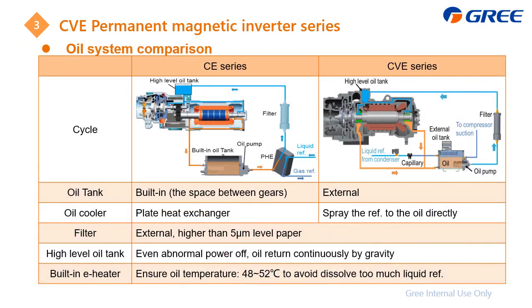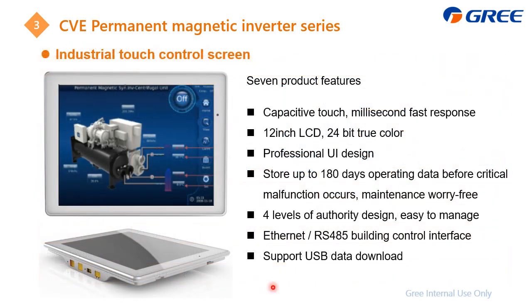And this is the oil system comparison between the CE and CVE series. I just compare the oil tank: this one is built-in and this one is external. As for the oil cooler, the CE adopts the plate heat exchanger, and for the CVE, we spray the refrigerant directly into the oil. For the filter, it is the same, with a target of 5 μm or above. The high level oil tank is also the same, located at a higher position. There is also a built-in e-heater to keep the oil temperature in this range. And this is the controller, and actually this part is almost the same as the CE series.